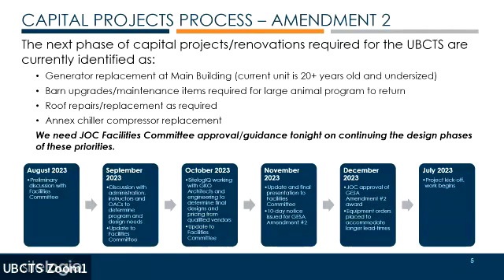You need to do a load bank test to verify that and verify all of the load. When our engineers look at all the circuits connected to it, you need at least a 250, if not a 280. That's where a load bank test comes into play, so we can actually test how much it's pulling. Is that based on maximum usage of everything in the building?